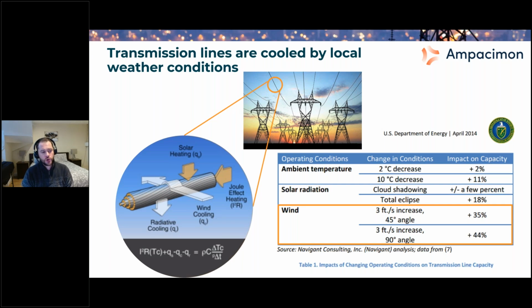But then you have two cooling sources or sinks, if you like. The one is radiative cooling, which is ambient temperature drives that. So if the ambient temperature is cool and colder than the conductor, you'll actually have a cooling effect. And the other one is convective cooling, which is from the wind. The wind blows over the line and causes it to cool.